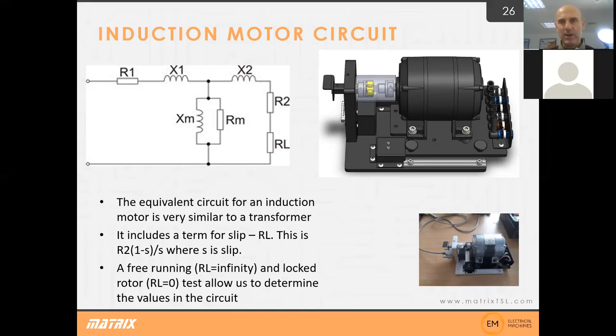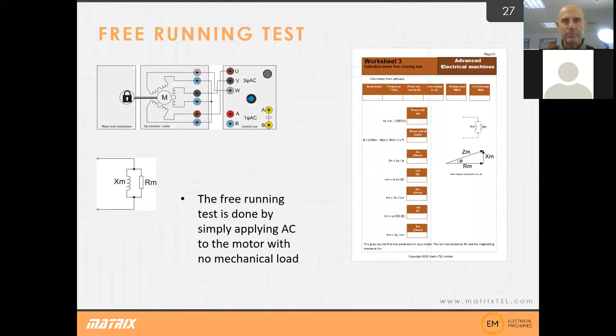But basically, if we know what the value of slip is, it allows us to make similar assumptions to the transformer. When we are free running, the slip is 0, so we can assume that the terms in the circuit are limited to the magnetizing components. So in a free running test, the magnetizing components are far greater than the other components in the system.